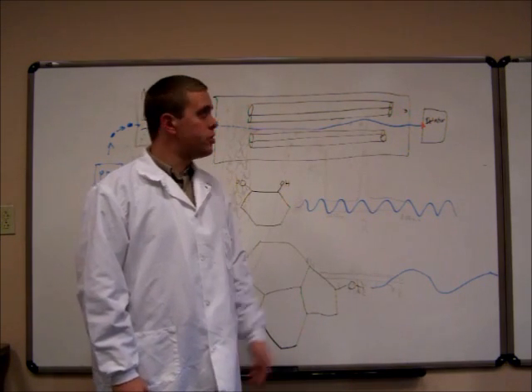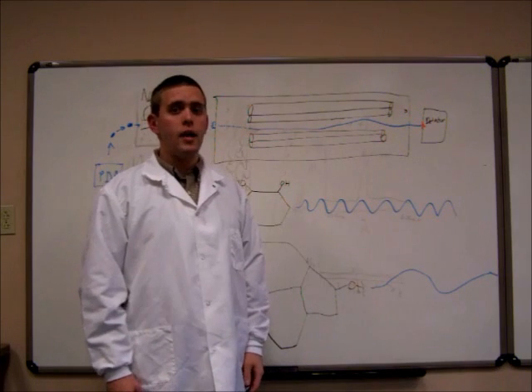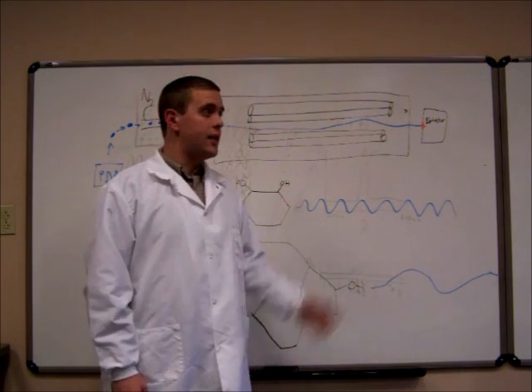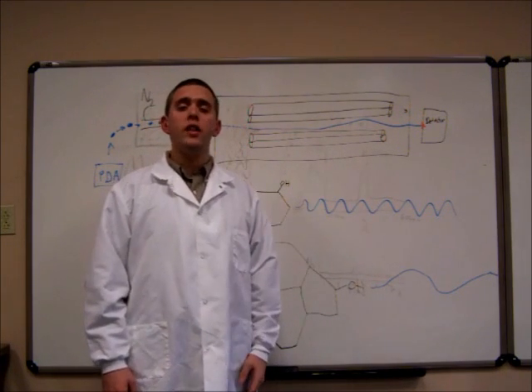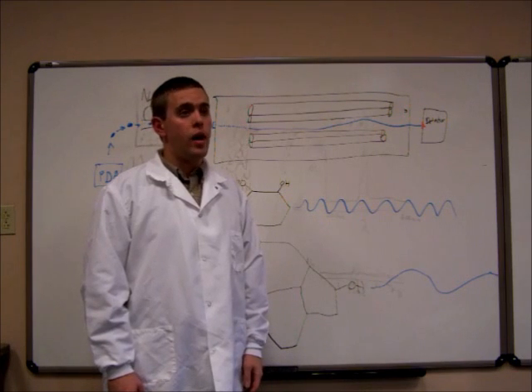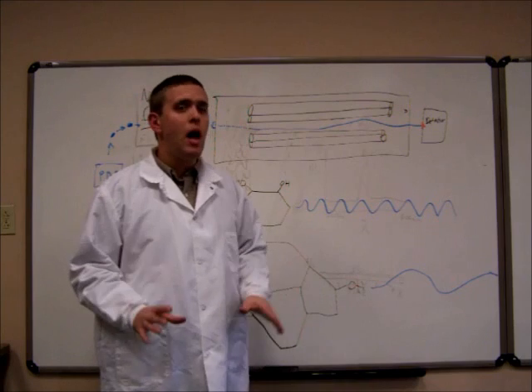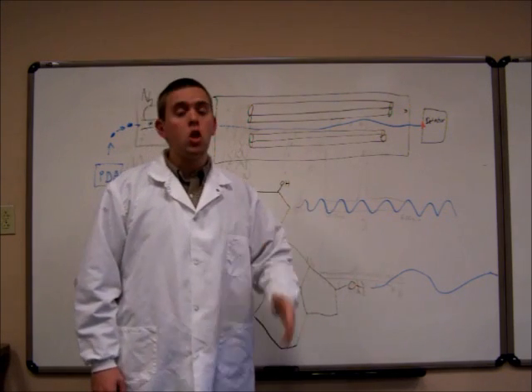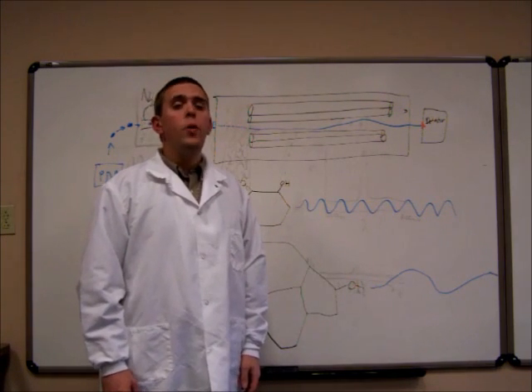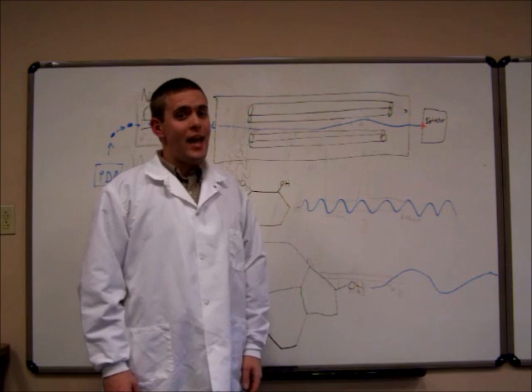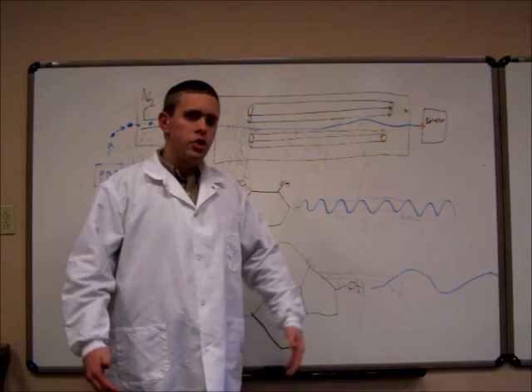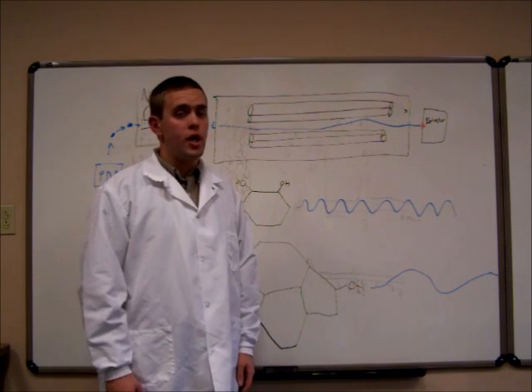So as you're running analytes through the instrument, make sure you're running them at a relatively low molarity within the micromolar to nanomolar range. The less molecules coming through this machine, the longer it can last. We know that this machine can pick up in the nanomolar to micromolar quantity, so let's keep it at that as we're working through the machine, just to prolong the life of the instrument.